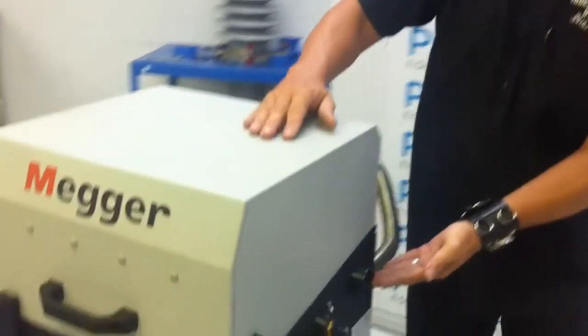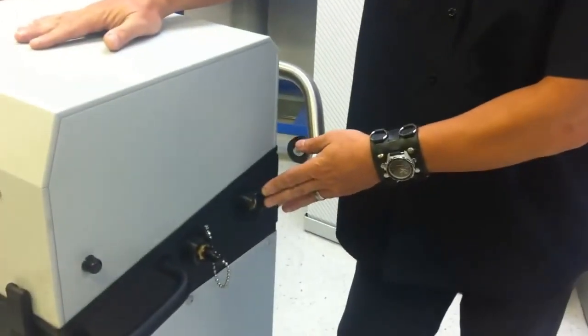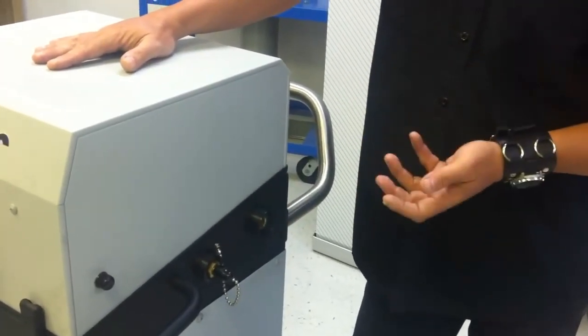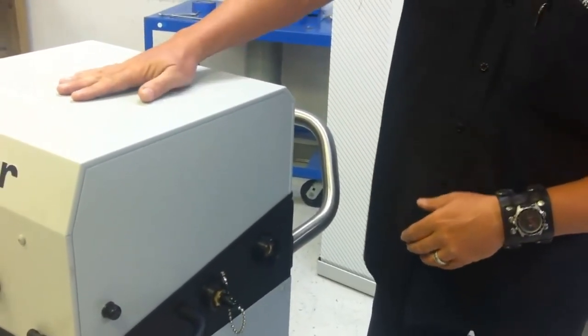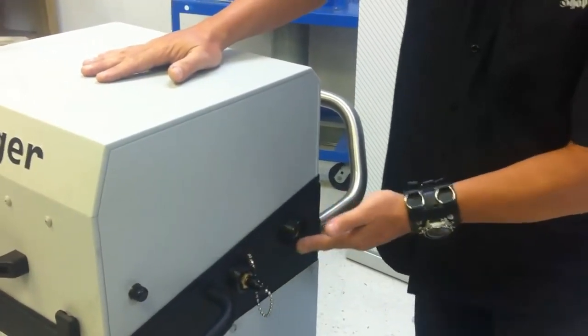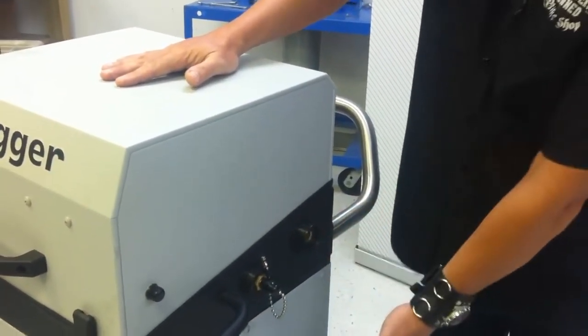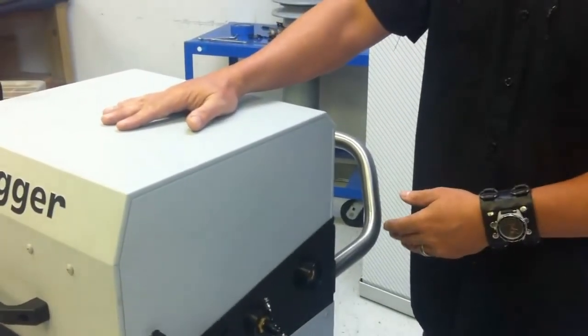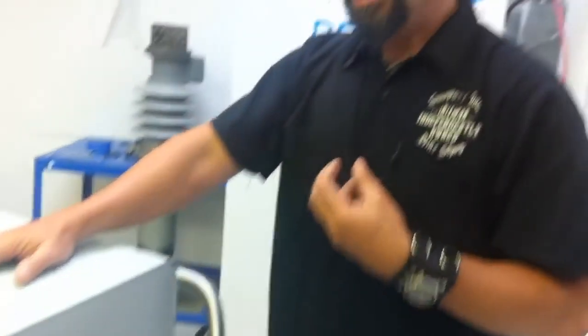a nice feature that we see over here is that the primary power source for this instrument is AC 120 volt service. However, Megger does have the built-in provision where it will accept a DC input. Built into the instrument there is a DC to AC inverter. So if we're, for instance, working at a wind farm where we don't have power, we can run this instrument by simply connecting the DC source onto the 12 volt battery of our truck, and we could actually run the instrument in the field without any local power available.